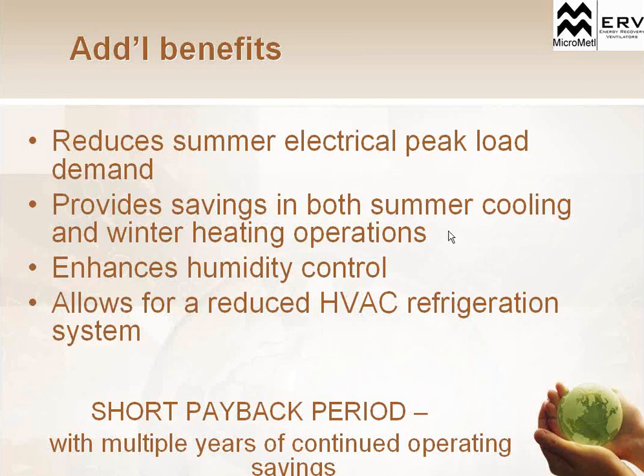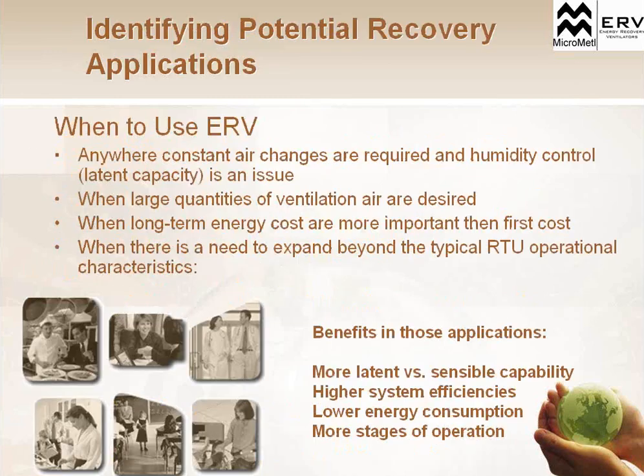Because of all these different reasons, because we're reducing electrical load, we're saving energy, we're reducing the humidity points that we have to control, we're actually going to have a very short payback on an energy recovery ventilator in conjunction with the standard HVAC system. So we'll talk a little bit about payback later, but typically we've seen 2 or less years payback on any type of energy recovery unit, and that's a very conservative estimate.